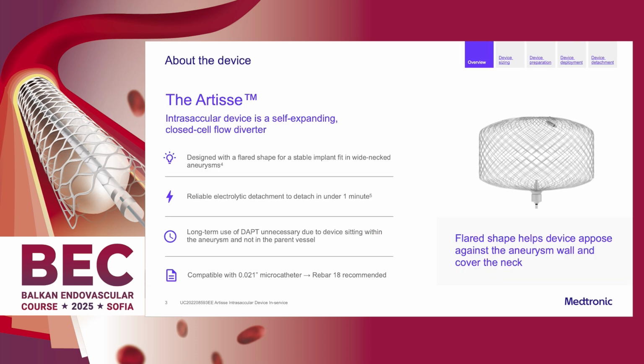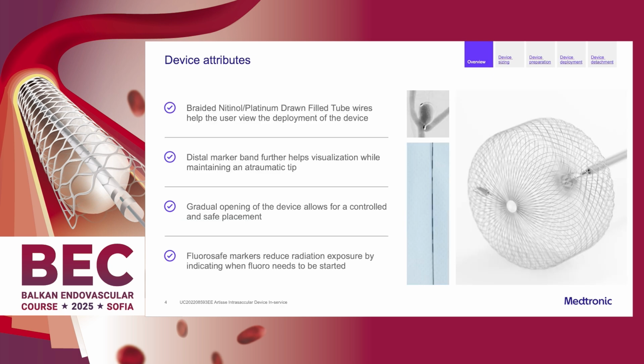About the Artisse device: the Artisse intrasaccular device is a self-expanding closed-cell flow diverter. It sits entirely within the aneurysm, eliminating the need for long-term dual antiplatelet therapy. Designed with a flared shape, it ensures a stable implant fit in wide-neck aneurysms. The device is compatible with a 0.021-inch microcatheter, with Rebar 18 recommended for optimal performance. Key device attributes: Artisse is constructed from braided nitinol and platinum drawn filled tube wires, enhancing visualization during deployment. A distal marker band aids in precise placement while maintaining an atraumatic tip. Gradual opening allows controlled and safe placement. Fluorosafe markers minimize radiation exposure by indicating when fluoroscopy should be used.